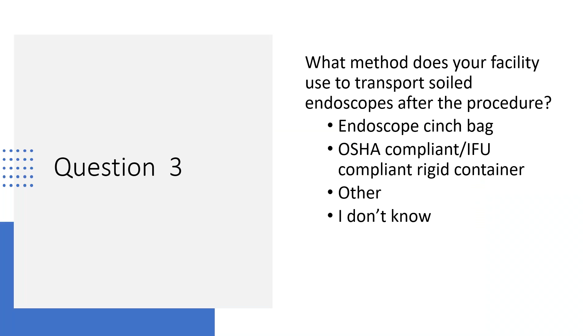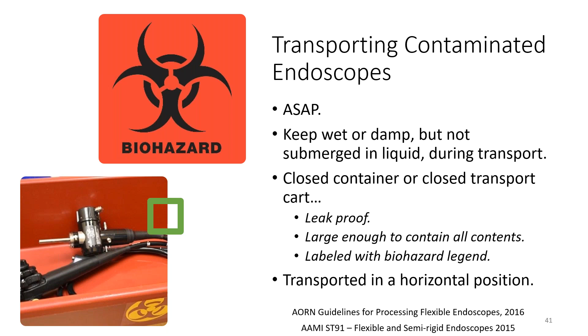But transporting contaminated endoscopes needs to be done as soon as possible. They need to be kept wet or damp, just like stainless steel instruments, just not submerged. And they got to be in a closed container, OSHA approved. Leak proof, large enough to contain all the contents, labeled with biohazard, and transported in a horizontal position. Again, this is from AORN and AAMI ST91, if you're not familiar. And here you'll see some examples.